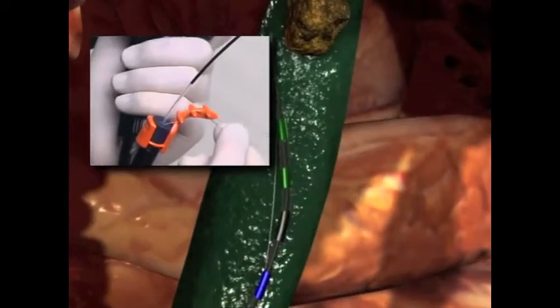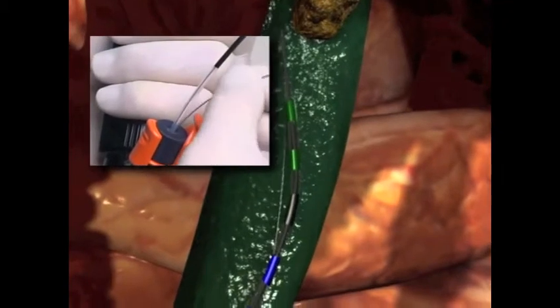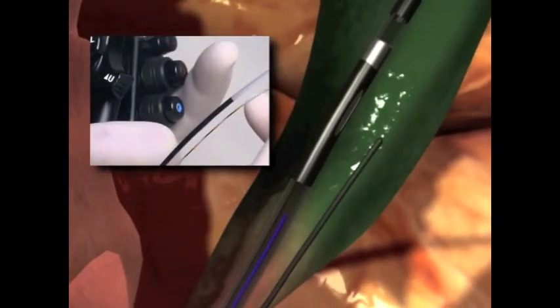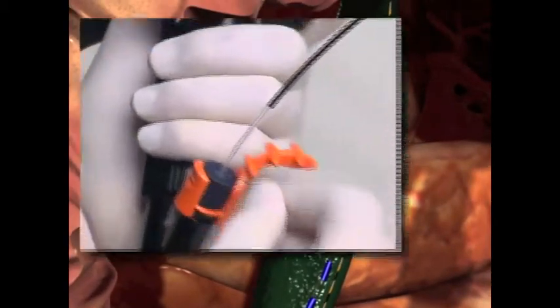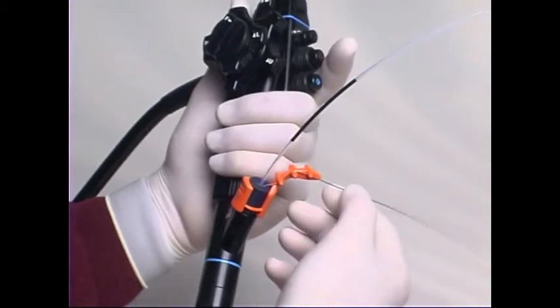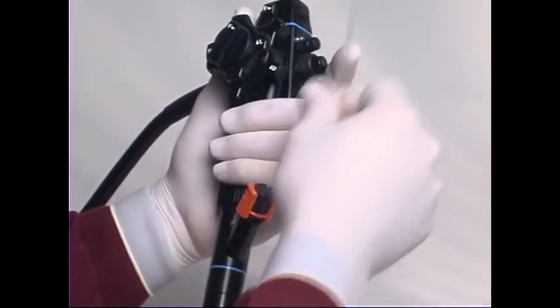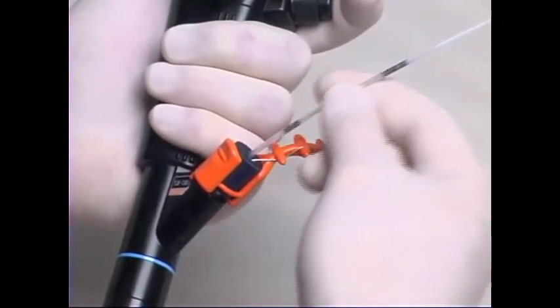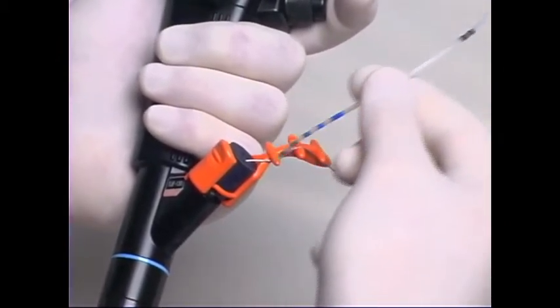Continue to pull the wire guide back until the IDE reference mark on the wire guide reaches the proximal end of the catheter IDE reference mark. This is a visual indication that the wire guide has detached from the catheter and an intraductal exchange has occurred. This can be verified fluoroscopically. Re-advance the wire guide to the desired position within the duct and relock the wire guide. The device is now free to be removed independently from the ultra-short wire.